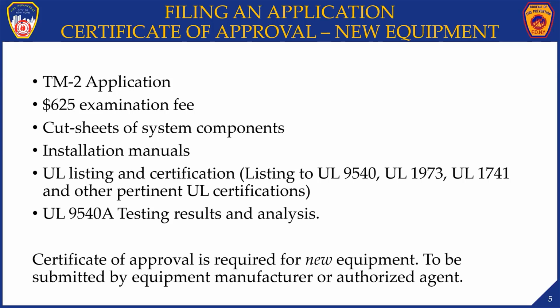Once approved and granted a certificate of approval, battery installers may use those systems defined in the certificate of approval for small systems as defined in 3 RCNY 608-01. Once granted a certificate of approval for those size systems, a battery installer could install those systems across NYC if the conditions outlined in the certificate of approval are met. For medium and large systems, the equipment needs to have gone through the certificate of approval process and a TM1 needs to be filed, since medium and large systems are approved on a site-by-site basis.